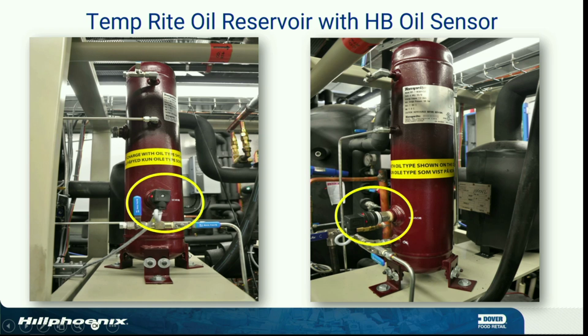But anyway, these are our HB sensors. They are capacitance style sensors. If you take that sensor, do we got pictures? I think the video's in this one, I'm not sure. Okay, the video might be in here. But anyway, it's got a well that goes in the fluid. You saw that, right? There's a well. This well right here. That's our well. The electronic part of that sensor will come right off. There's 2 to 3 2.5mm set screws on there for removing the sensor. You can take the sensor out.